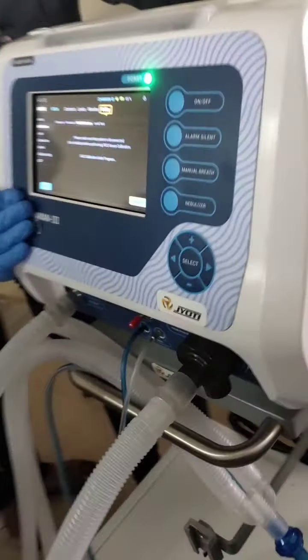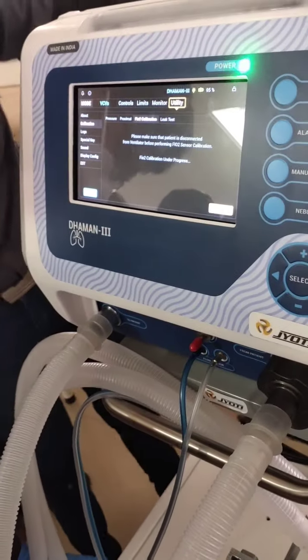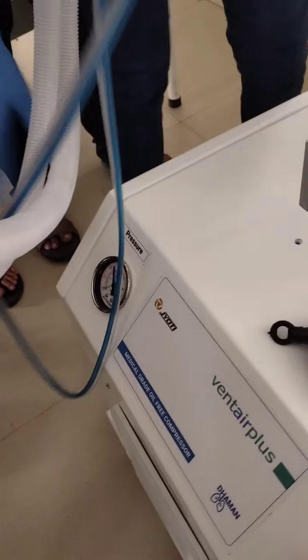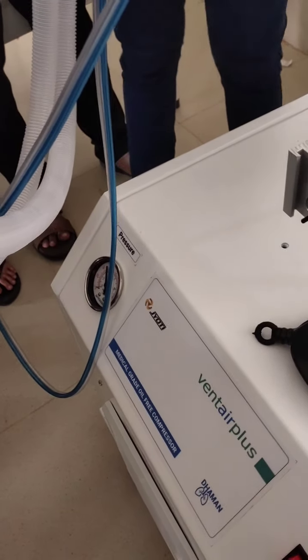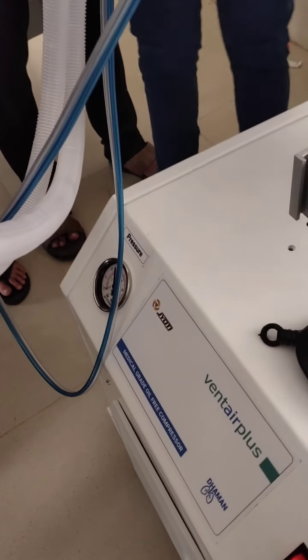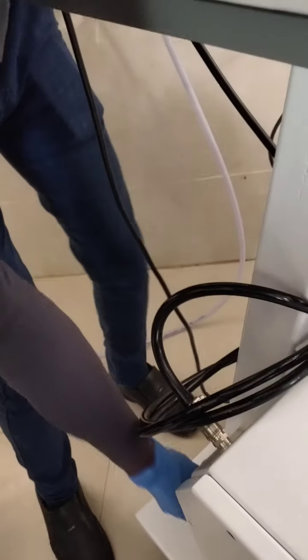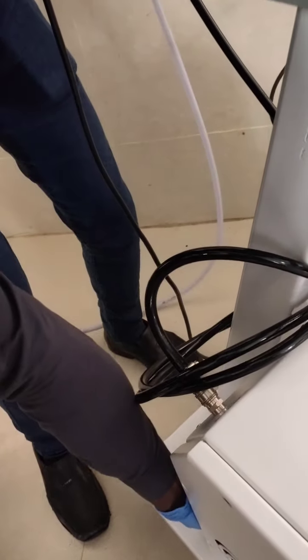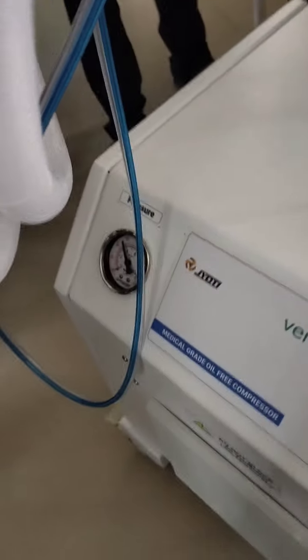Generally we face some air compressor issues, where sometimes the pressure won't come up to 60. It may show 0 or 30 or 60, whatever value, but the instrument shows the pressure is not coming from the air. At that time, on the backside we have the waste bottle tubing. You have to push and take it out, and close this part with your hand for 2 seconds. If you close it for 2 seconds, the air will pump out and pass, and the pressure will improve. This is the basic one.